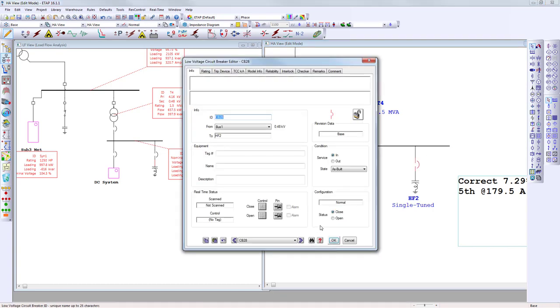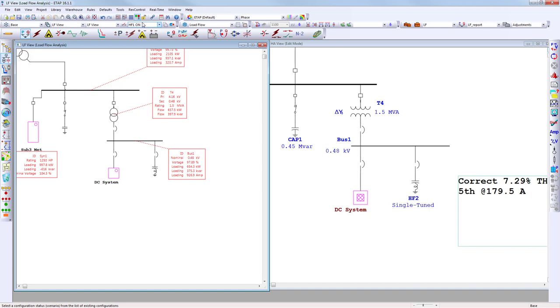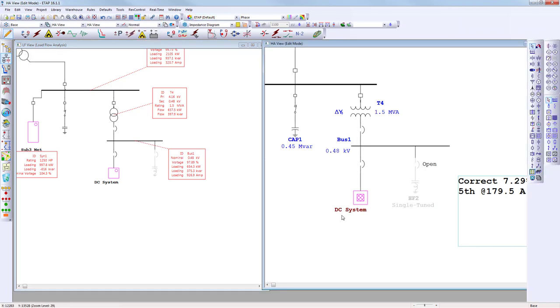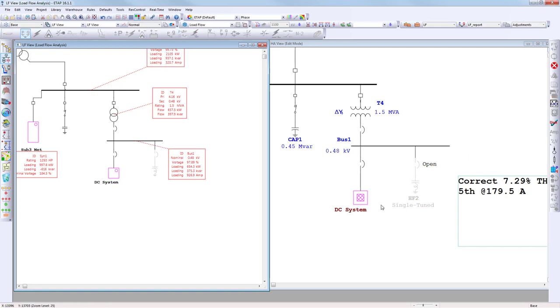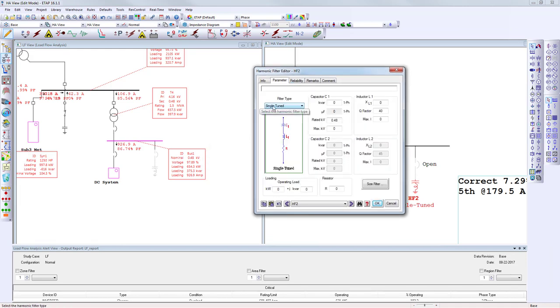When switching from normal to on, the filter becomes active. To begin sizing the filter, open the filter editor and go to Parameters. This will be a single-tuned filter. The rated kV is the single-phase capacitor rating: 480 V divided by the square root of 3, giving 0.277 kV. The maximum kV — the three-phase rating — is 0.48 kV.